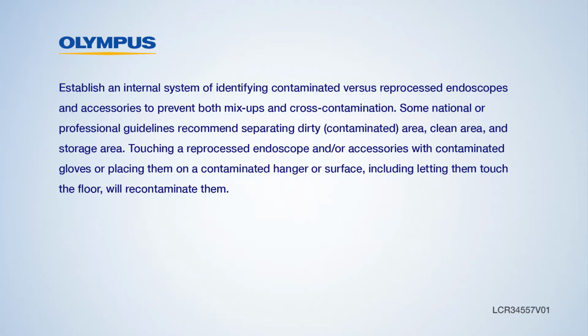Establish an internal system of identifying contaminated versus reprocessed endoscopes and accessories to prevent both mix-ups and cross-contamination. Some national or professional guidelines recommend separating dirty, contaminated area, clean area, and storage area. Touching a reprocessed endoscope and/or accessories with contaminated gloves, or placing them on a contaminated hanger or surface, including letting them touch the floor, will recontaminate them.